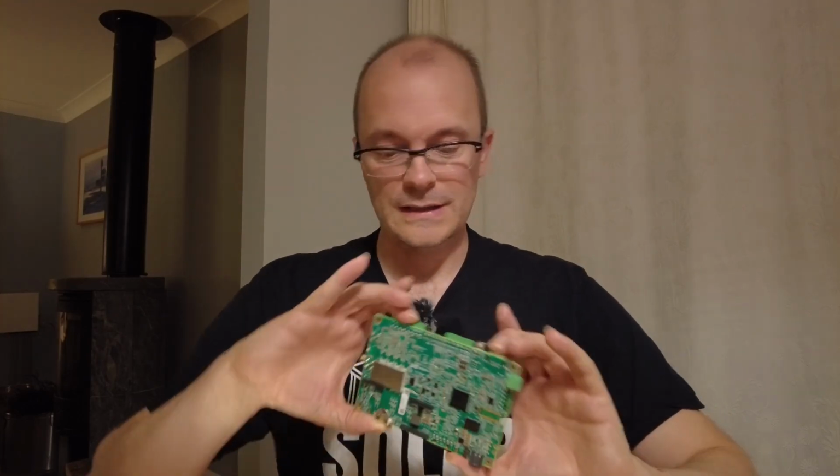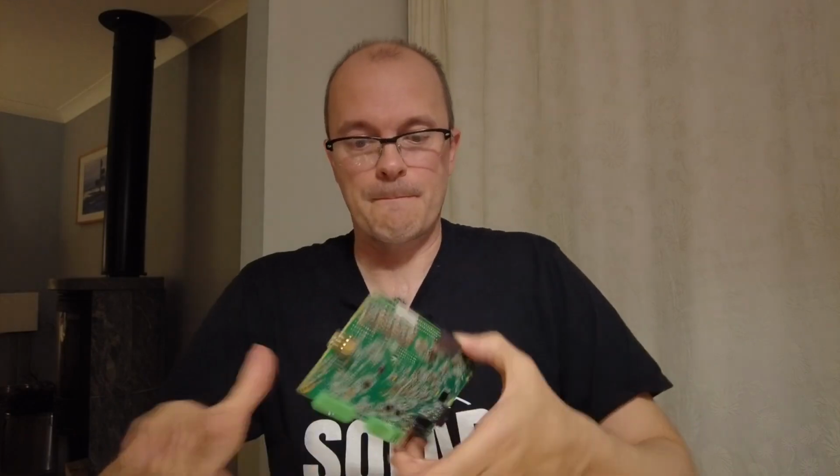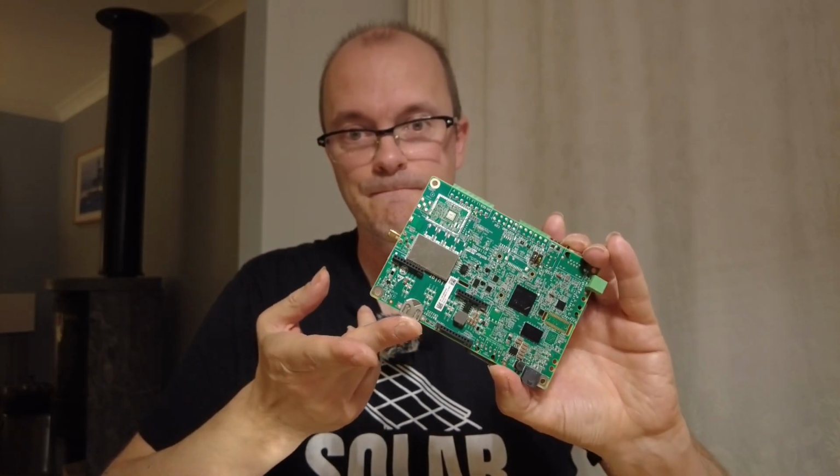The other thing you'll notice here, there's a battery. Little button battery. Typically you have them on motherboards to keep BIOS settings. I sometimes wonder why they didn't suggest pulling the battery out just to clear settings. Maybe that would have made all the difference, and it would have saved 5 weeks worth of delay in getting this unit commissioned. The other possibility is corrupt storage memory.